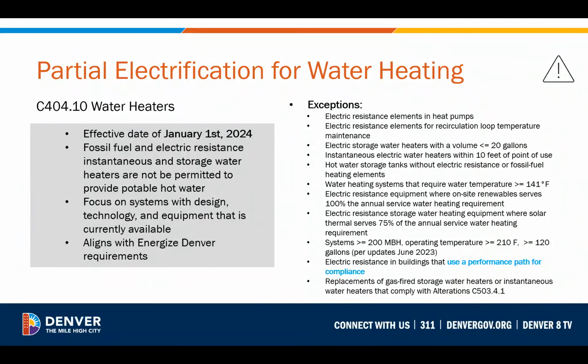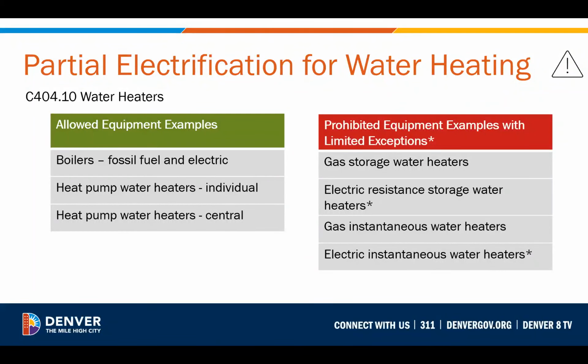And again, this is aligning with the Energize Denver requirements. You can see there's a lot of exceptions, so make sure you're referencing the code to see all the exceptions, some notable ones being electric resistance backup for heat pumps. If you have certain temperatures that you're required to hit, if you're using a renewable form of solar thermal, so several of those. And again, we have that same one where you can use electric resistance if you're complying with the performance path and the total building is still meeting the performance path requirements of the 2022 Denver Energy Code. So again, these lists are just examples to give you an idea, reference the code in detail if something you're curious about is not covered here.